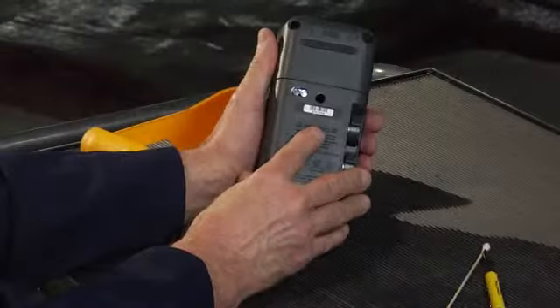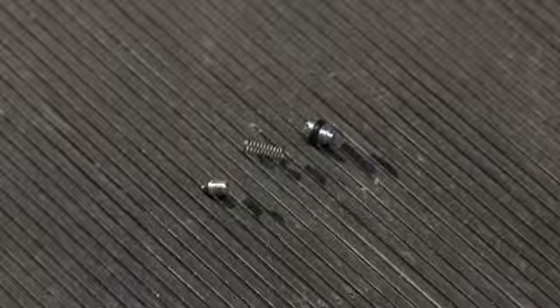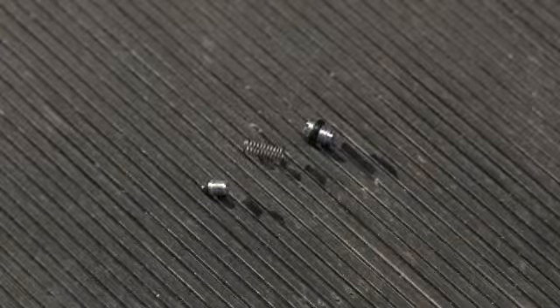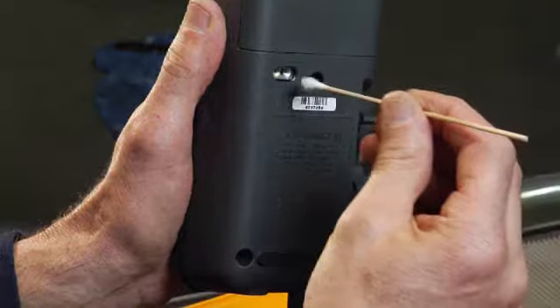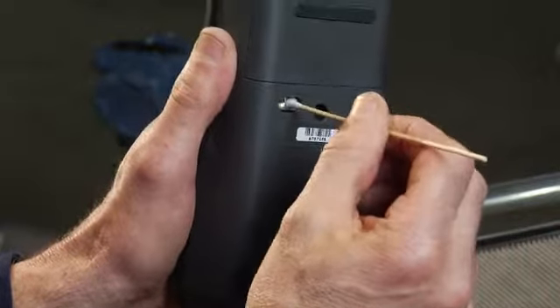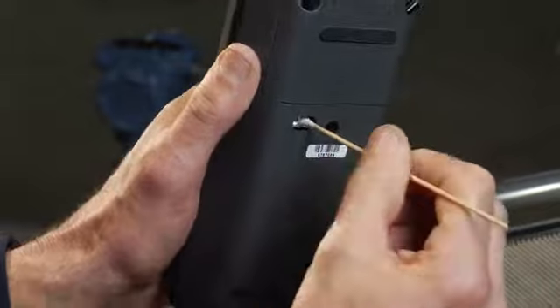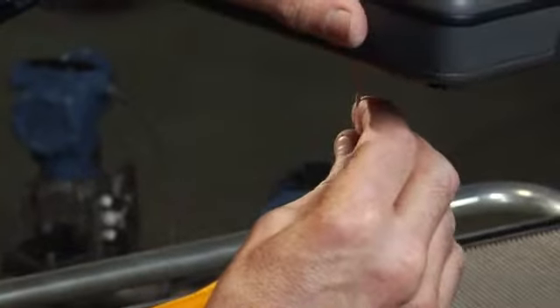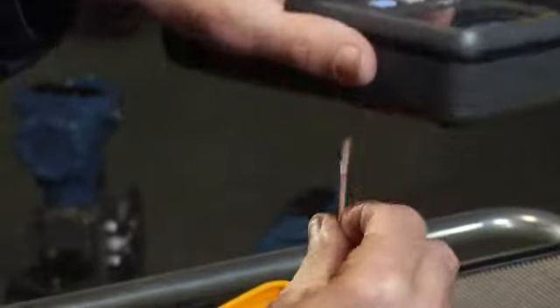Use a good level workplace where you can capture the small parts. The removed parts include the check valve, the tensioning spring, and the cover screw. Once you've removed the small parts, clean out the chambers with a cotton swab to remove the fluids. To clean out the chamber, insert the Q-tip and rotate to clean out the fluid and then remove.